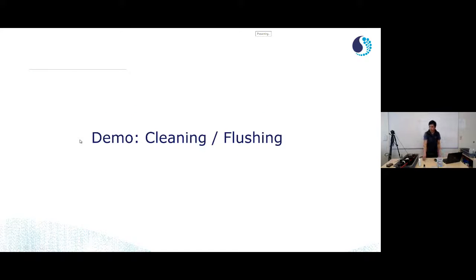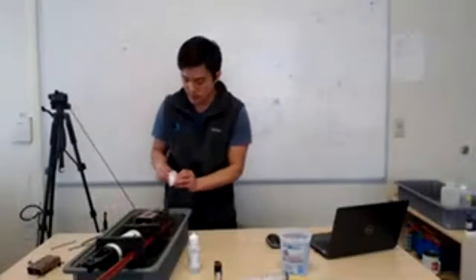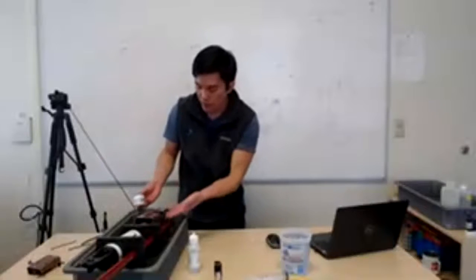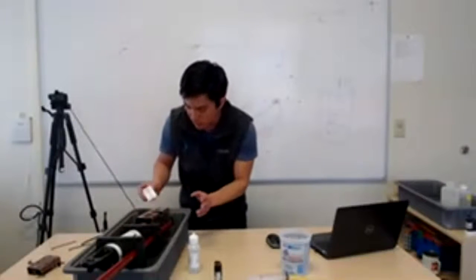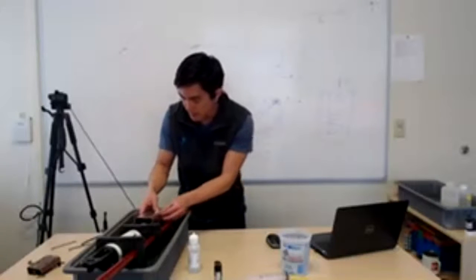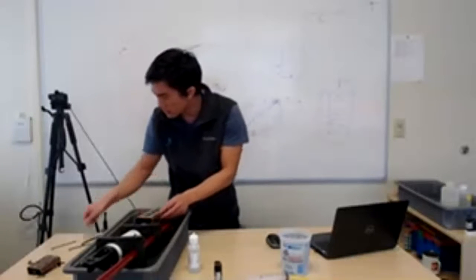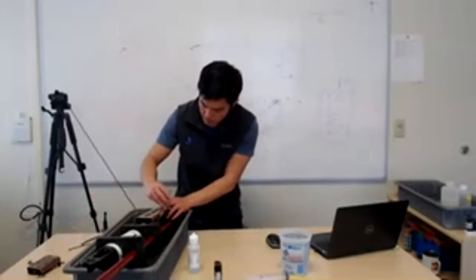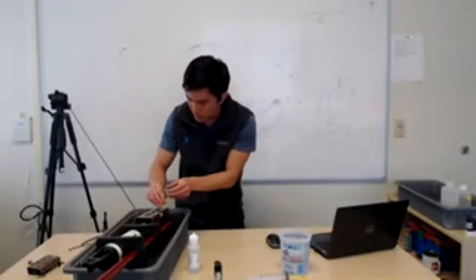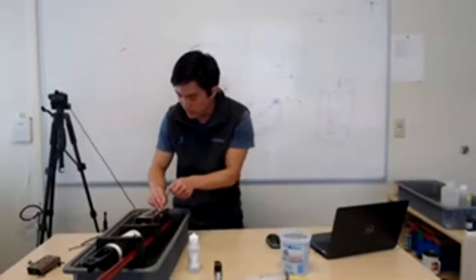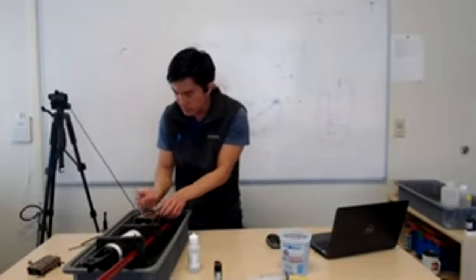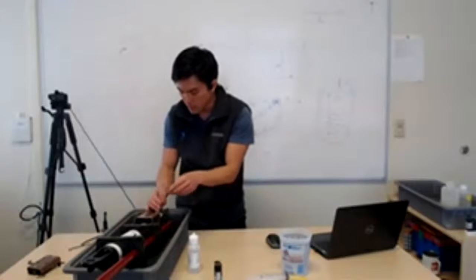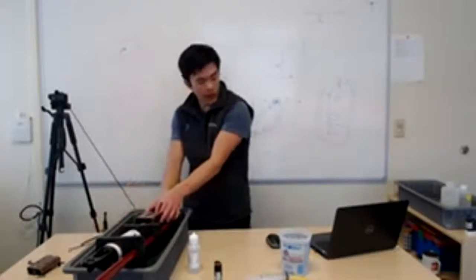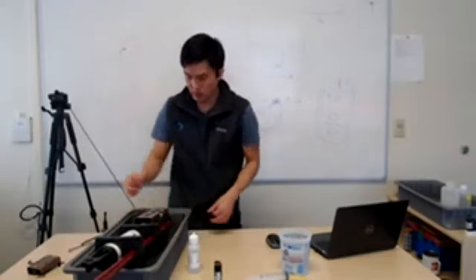Okay, so the very last thing I wanted to do is demonstrate the cleaning and flushing procedure. And actually, one thing I forgot to do was reinstall the dummy block for the pH sensor onto my HydroCAT EP. So I'm going to inspect the connector, make sure that it's clean and dry, and then take the dummy block, install it into the body, and as with the pH sensor, carefully tighten it down, making sure not to over tighten these screws, getting it just snug, and then wiggling it back and forth to make sure that it's properly in there.